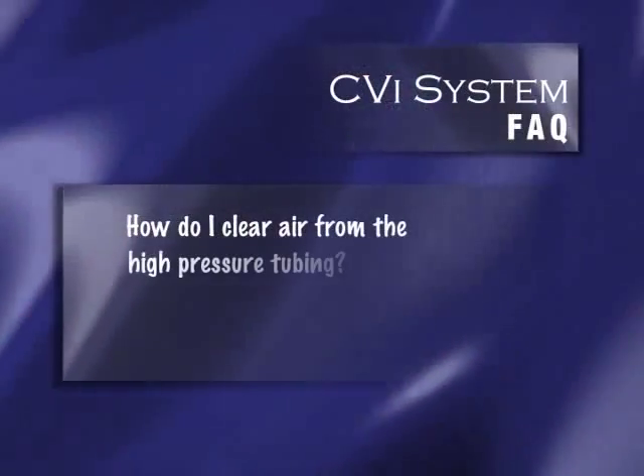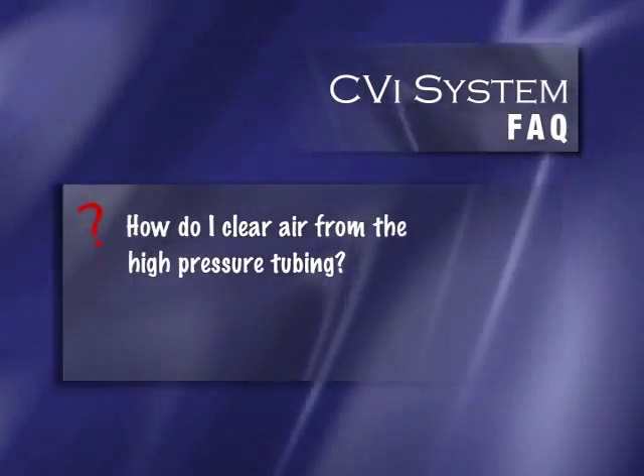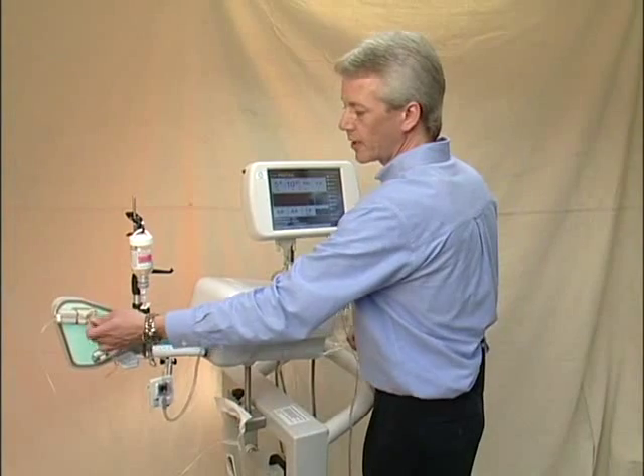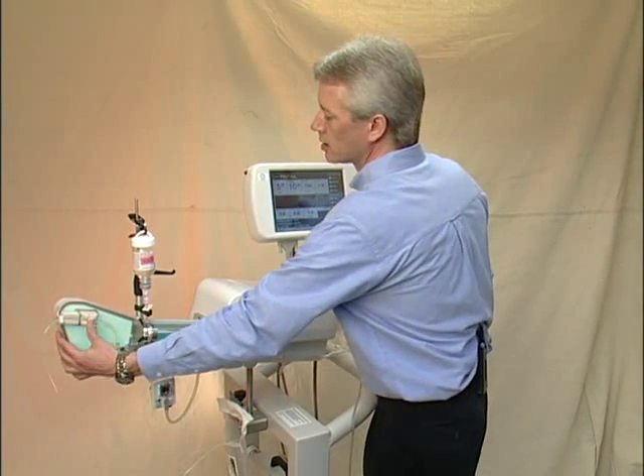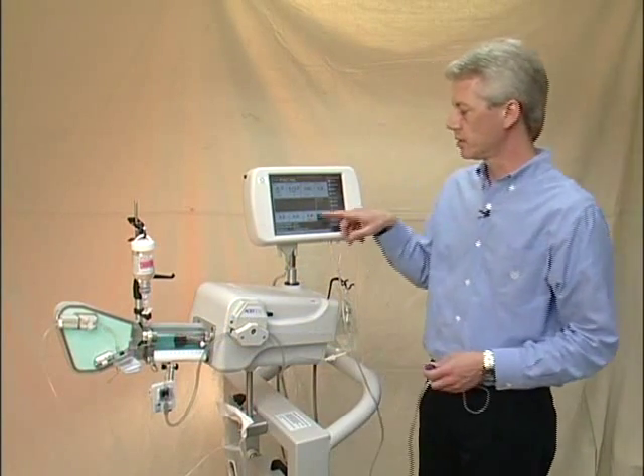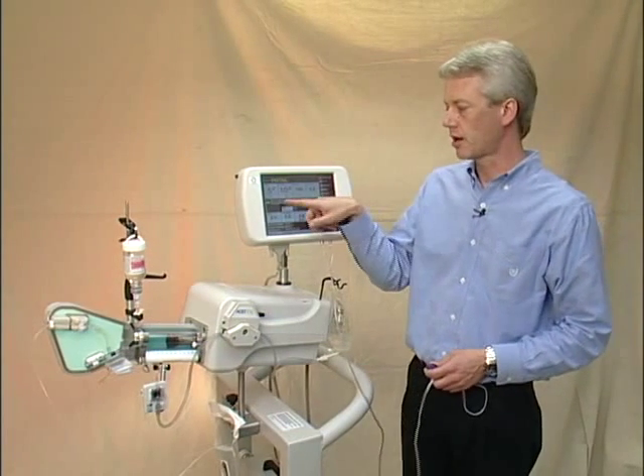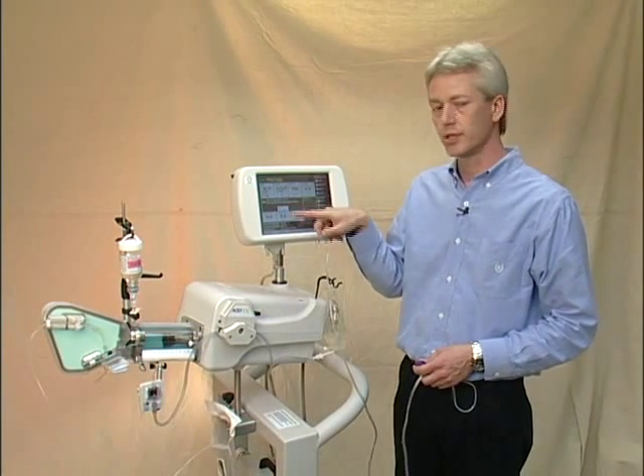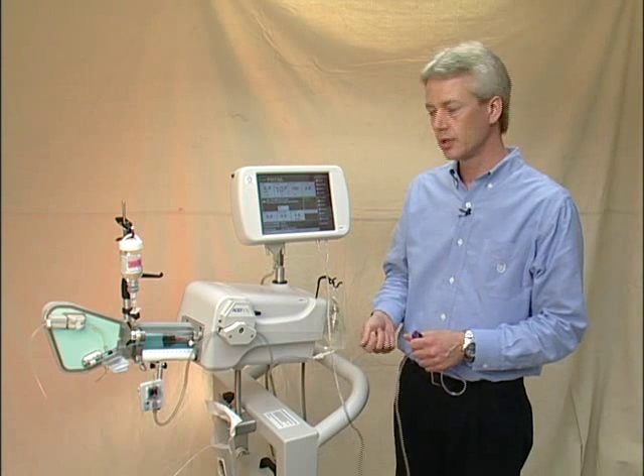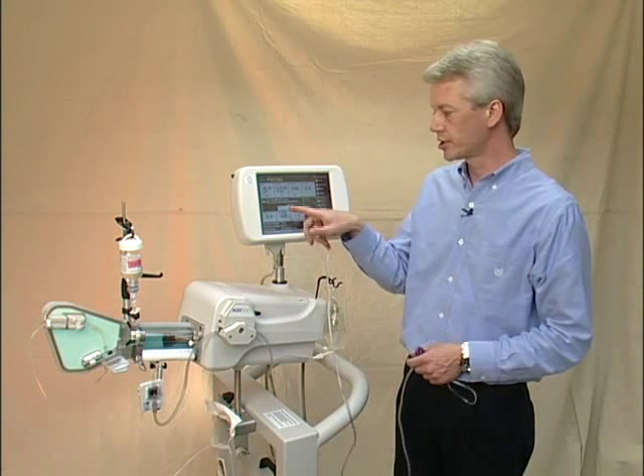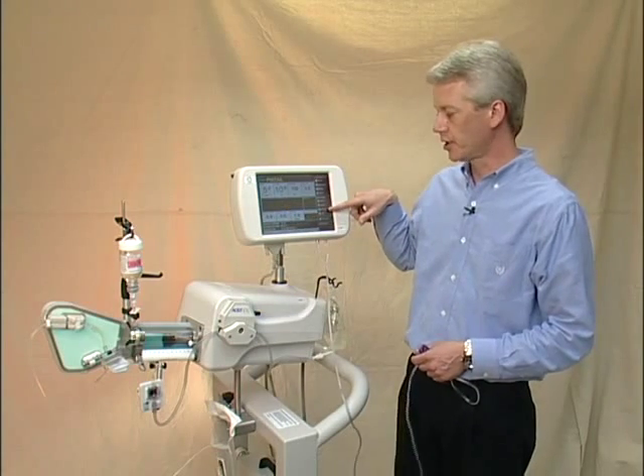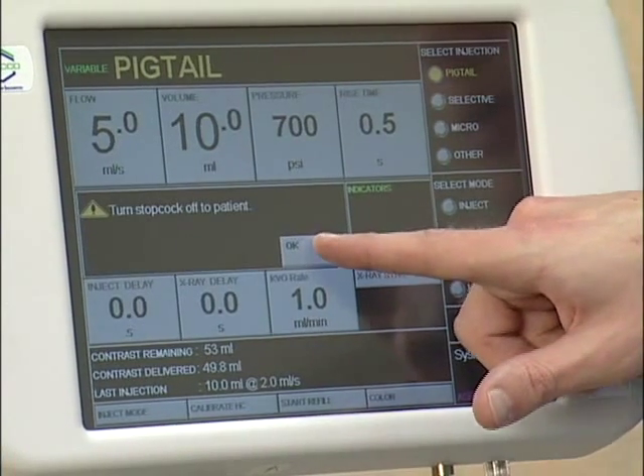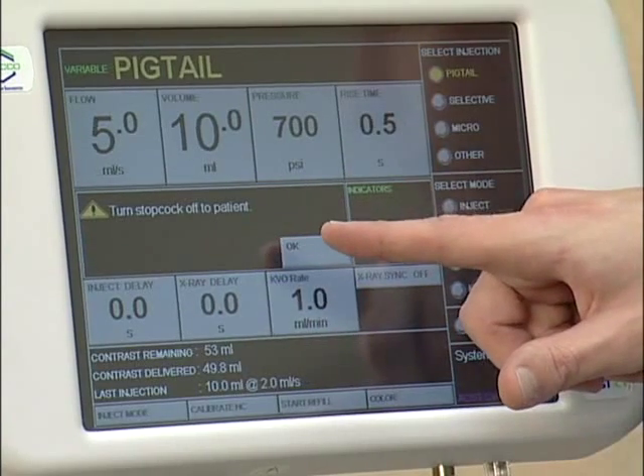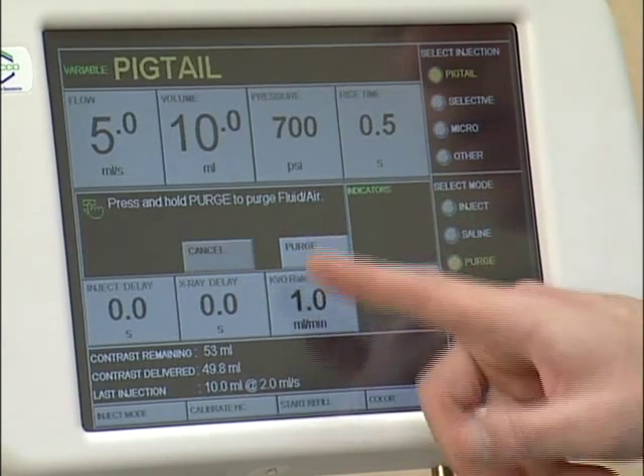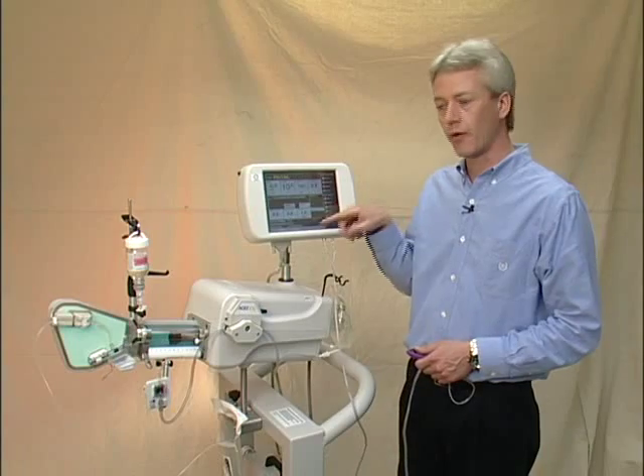That will enable the contrast to be delivered from the catheter tip without it ejecting from the artery. How do I go about clearing air out of the high pressure tubing? Clearing air from the high pressure tubing, the system will actually prompt you if you arm to inject and it will say air column detect. The message on the screen is to turn the stopcock off to the patient and press purge. So the physician would do that by selecting purge on the screen. Again, one more reminder to turn the stopcock off to the patient, and then a generous purge to allow the air to be removed from the side port of the stopcock.